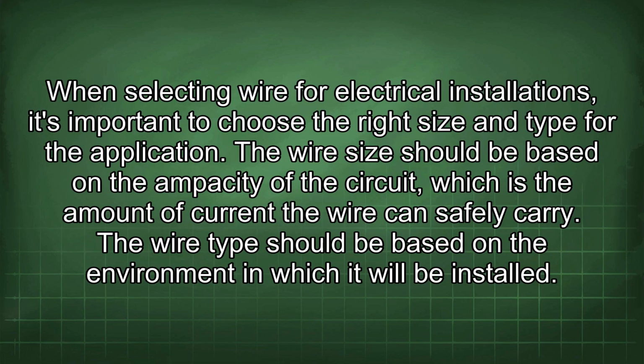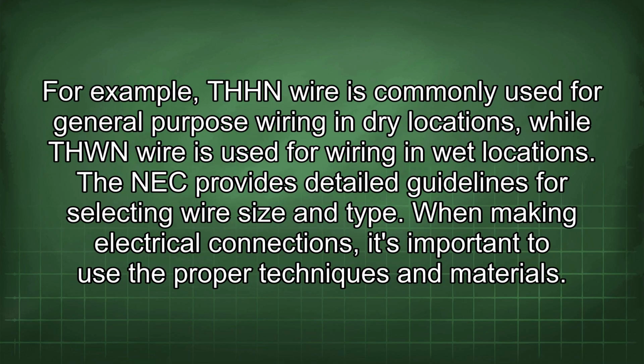When selecting wire for electrical installations, it's important to choose the right size and type for the application. The wire size should be based on the ampacity of the circuit, which is the amount of current the wire can safely carry. The wire type should be based on the environment in which it will be installed. For example, THHN wire is commonly used for general-purpose wiring in dry locations, while THWN wire is used for wiring in wet locations. The NEC provides detailed guidelines for selecting wire size and type.